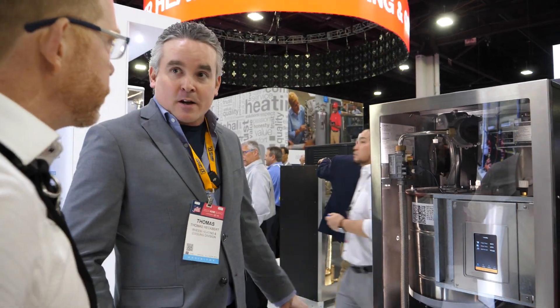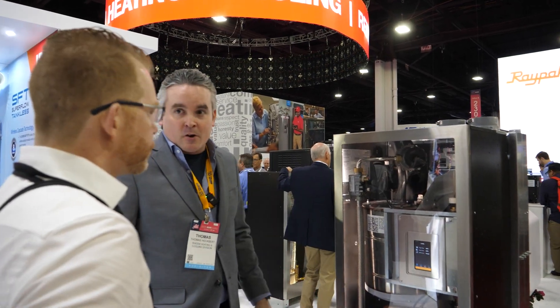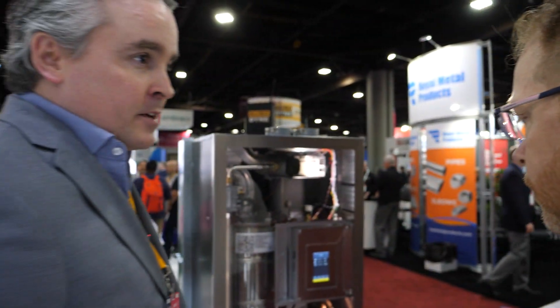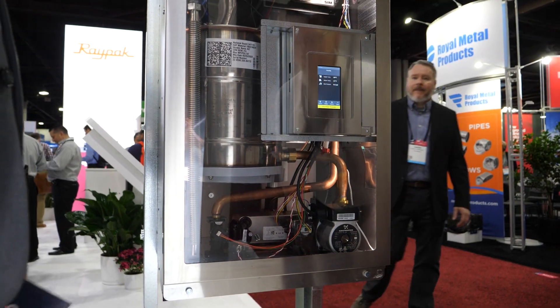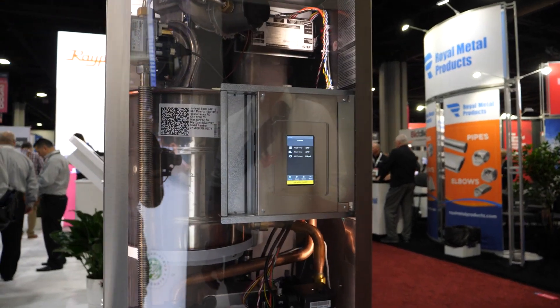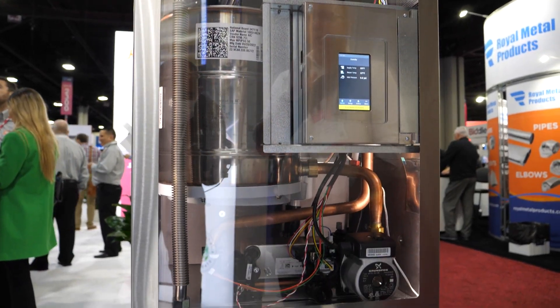The combi market is the ever-growing market for boilers. We have combi options from our Super Flow series, but we wanted something in the stainless steel product using our V10 control, which is an extremely popular and powerful control for us. Hence the CX. We use an oversized Grundfos combi block and intentionally put in too many plates so that scaling and fouling that can happen over the years will take longer to become an issue. It has a diverter valve built in, and we have these in multiple test sites working extremely well. This product is launching within a couple of months.